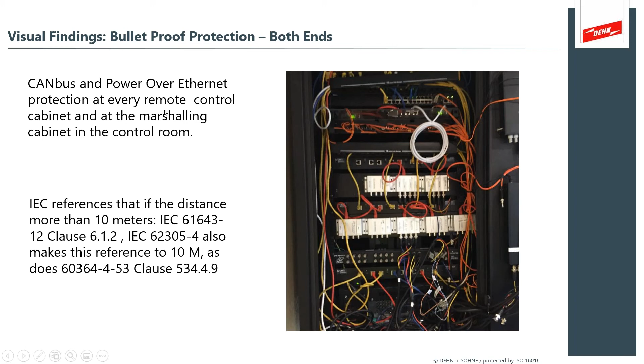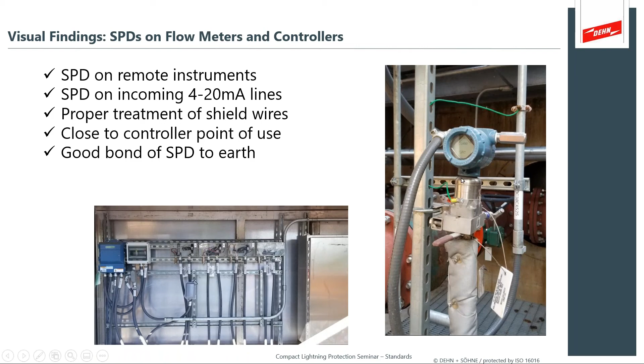Visual findings. We're looking for things at the flow meters. We're looking for good bonding of the SPD. We're looking for proper treatment of the shield wires and devices close to the point of use. So these are the things we're looking for as best practice. Here you can see the surge protection device is installed directly at that flow meter for best point of use control.